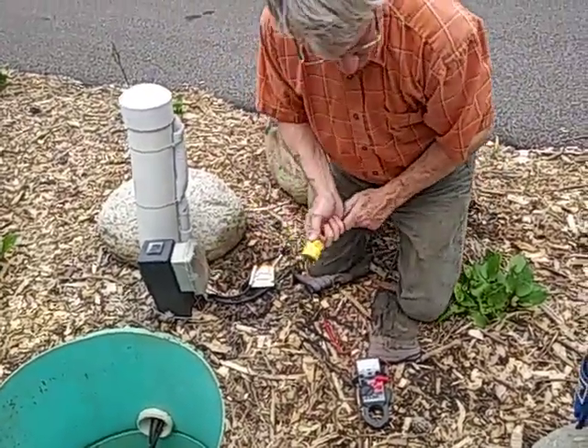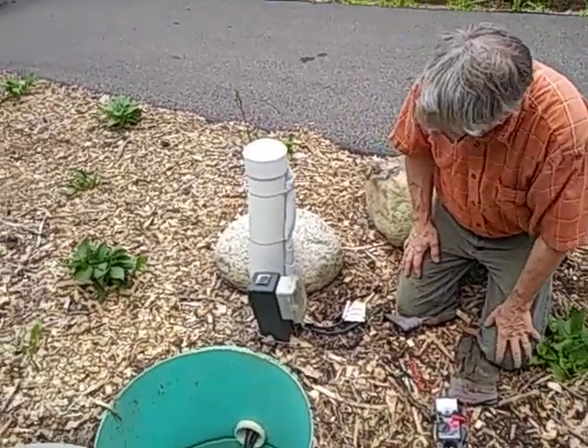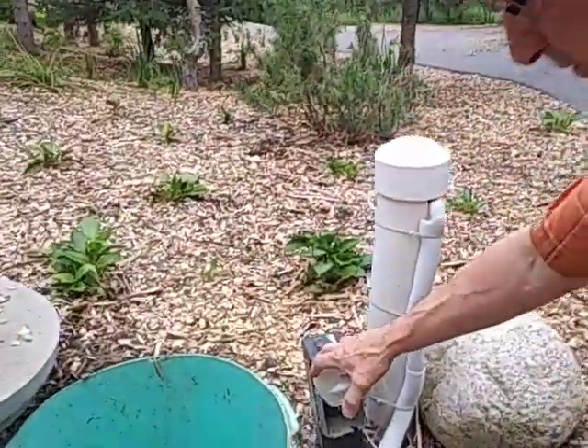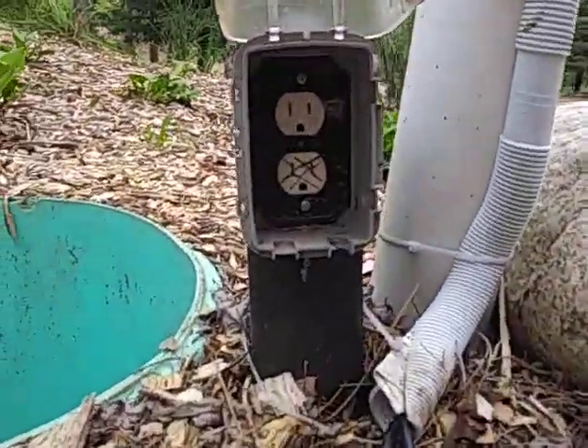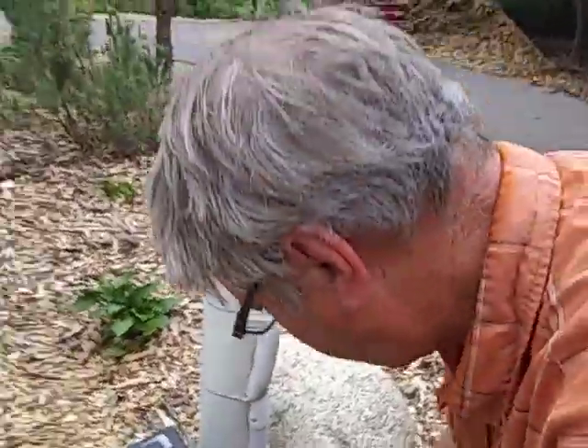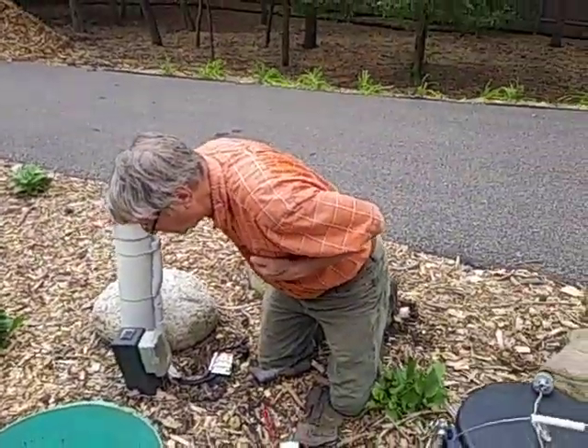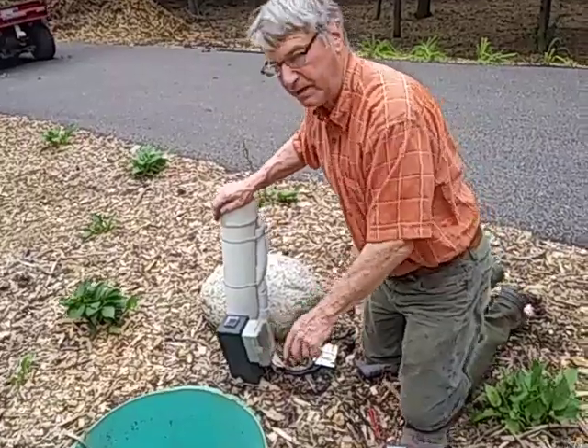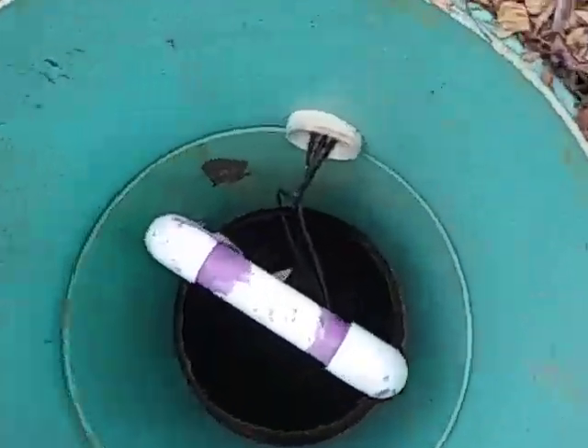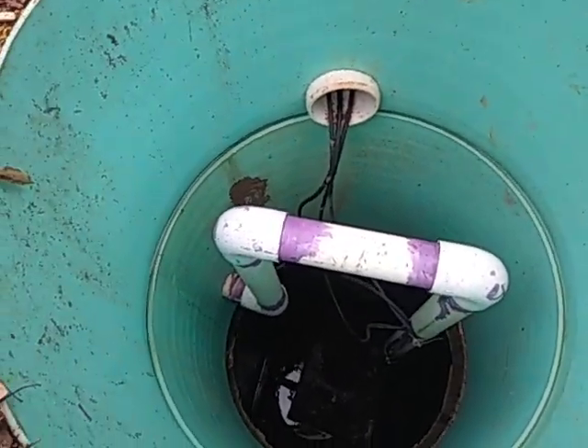When they wire these guys up, it's required to have a dedicated circuit. If you get down here real close and look at that outlet, that is not a legal outlet he's got in here. Some of these electricians — if you look at how the cords run up, some of them you open up the manhole and it looks like a spaghetti factory. But you can see all our wires are neat and orderly.